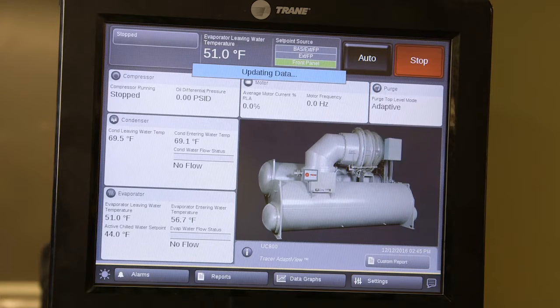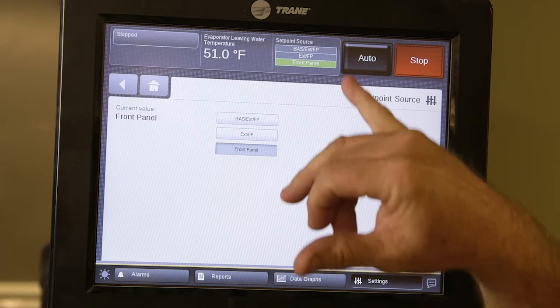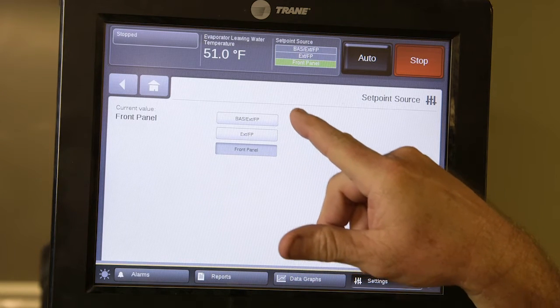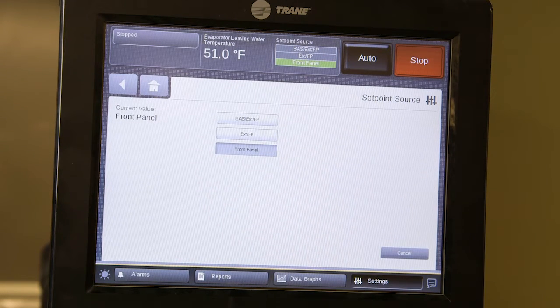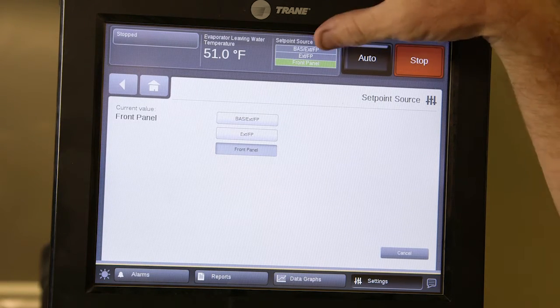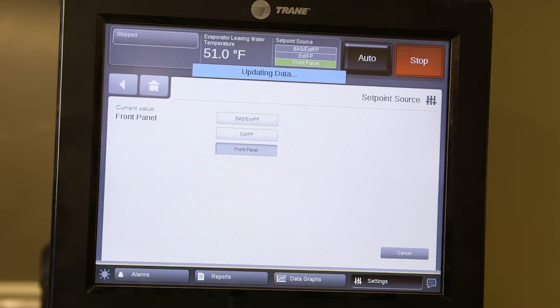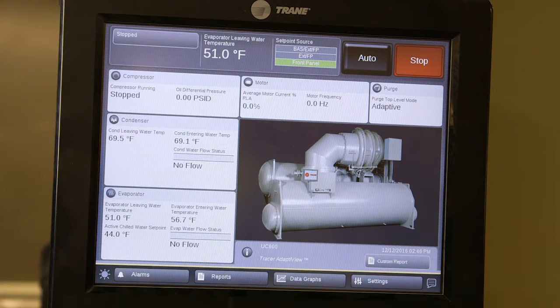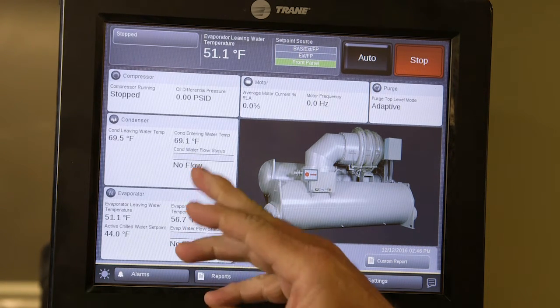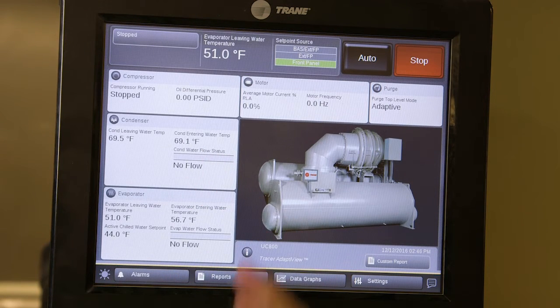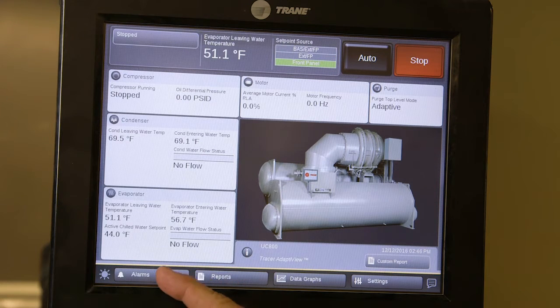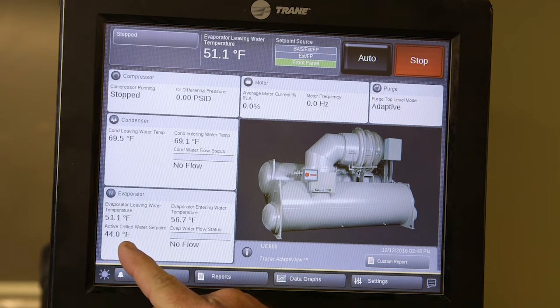You can change the operating mode by pressing the top menu screen, getting to the display screen, and pressing accept or acknowledge to change it. On the main menu, the compressor is currently stopped with no differential oil — that would normally run somewhere around 22 PSID. You can also view condenser entering and leaving temperatures and flow condition through the chiller, and the same for the evaporator. The evaporator chilled water set point is located on the main screen.